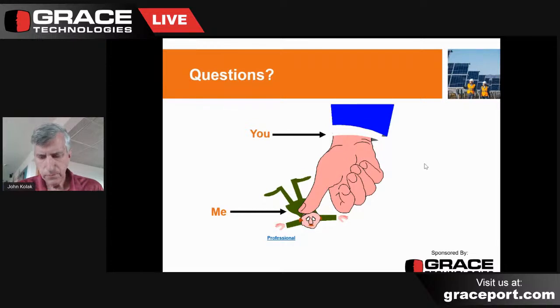Okay. So the next one I have is, why is an arc flash study considered differently from a relay coordination study? Why is it different? Well, a relay coordination study is part of an arc flash study. Normally, we have to take that into consideration. But what is a bit different about them is that with relay coordination, we're mostly interested in the system tripping out in the right order. And in an arc flash study, we're interested in lowering the incident energy. So why that's important is in some cases, you may have two overcurrent devices in series with each other. And from an arc flash standpoint, we don't care which one trips out because the net result is the same. You're going to lose the function of the device. From a coordination standpoint, we'd be unhappy with that because we took out a larger part of the system than we'd really want to take out.